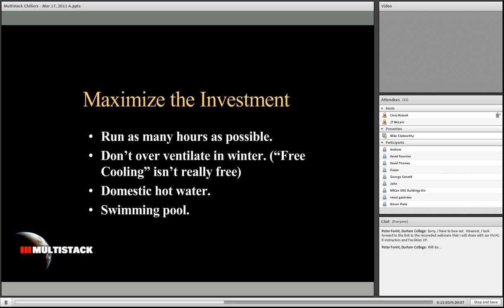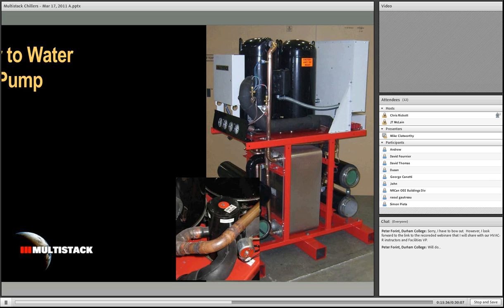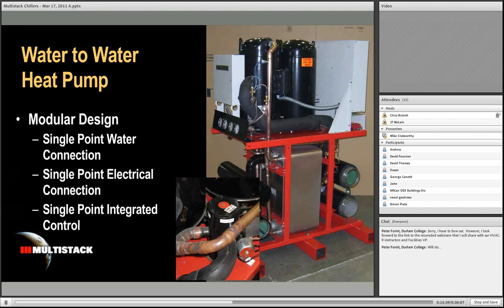This also should show a dedicated heat recovery payback curve based on a varying natural gas cost. Where we're going with all that is that the way to maximize your investment for dedicated heat recovery is to run the dedicated heat recovery chiller as many hours as possible. And this is one of those situations where oversizing the DHRC does not actually get us anything. In order for this to work, we have to be making hot water and cold water continuously. Also, don't overventilate in winter. Remember, we said that free cooling isn't really free. And then use the hot water in as many places as possible.